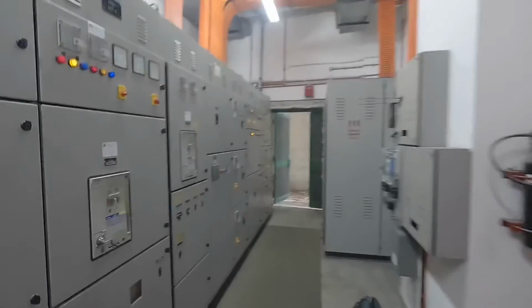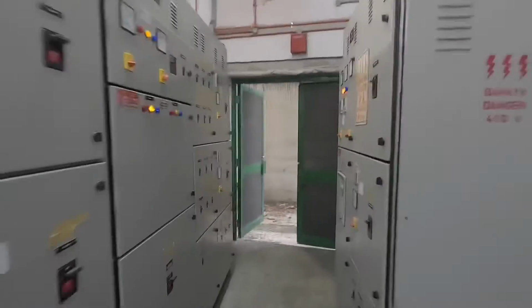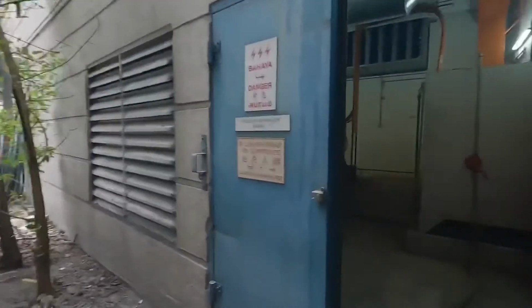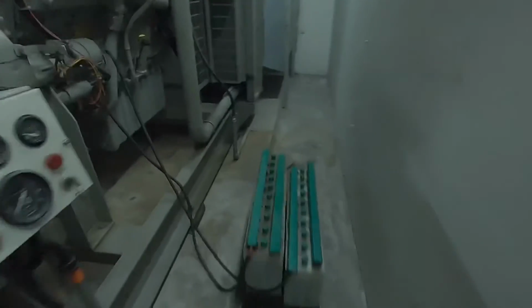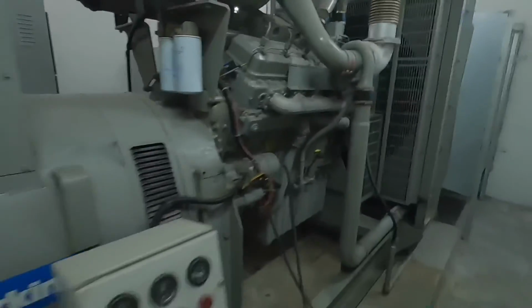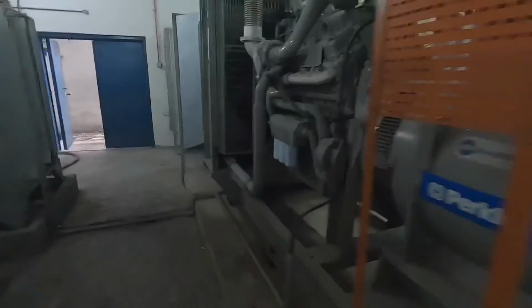Okay, before we close back the door at the genset room, let us visually check one more time. Make sure the genset physically is in good condition after running. Okay, no fuel leakages, no engine oil leakages, no radiator water leakages. Battery is in good condition. Voltage still okay. Genset can start, can stop automatically. That means cranking no issue.